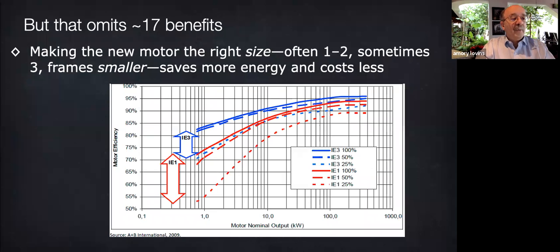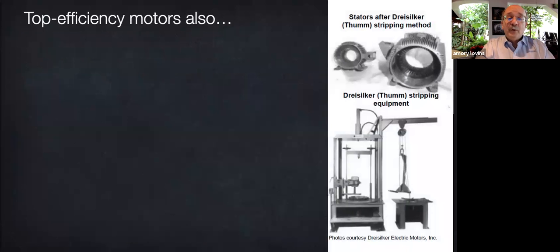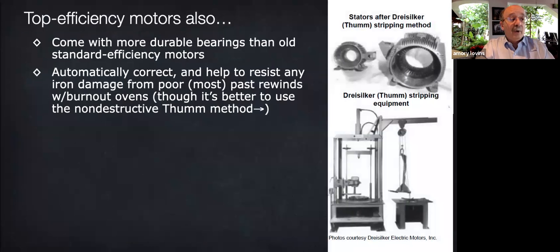So making the new motor the right size saves more energy, saves other costs. And the most efficient new motors also have better bearings. Bearing failures are the cause of 3/4 of mid-sized motor failures. The most efficient new motors automatically correct and they reduce susceptibility to hidden iron damage, which GE found wastes $1 to $3 billion a year of US electricity.